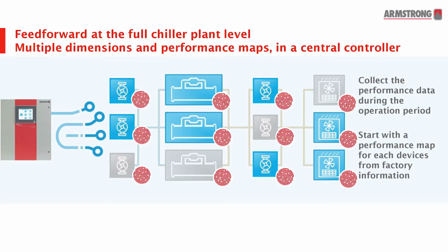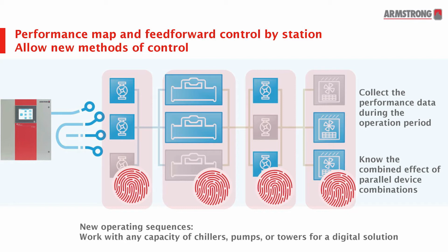With that same approach to fingerprinting a piece of equipment, we can do the same for all the devices in the chiller plant. That includes the chiller itself and the cooling towers, which is a 5-dimensional space. The chillers are a 9-dimensional space of performance mapping. We can create these performance maps, which let us start looking at combinations of equipment and the impact of those combinations in real time.